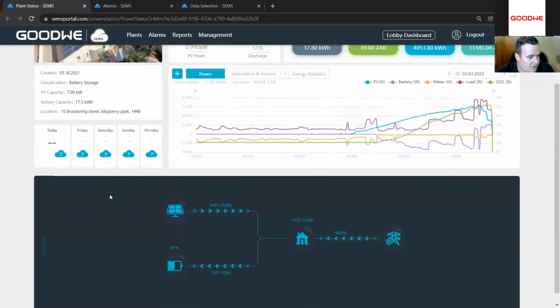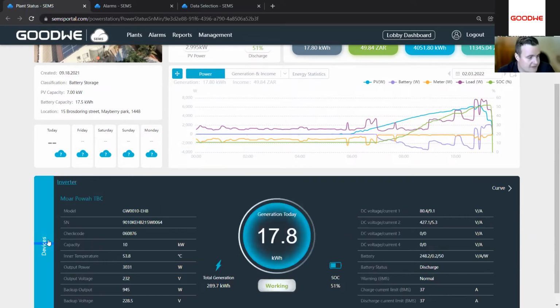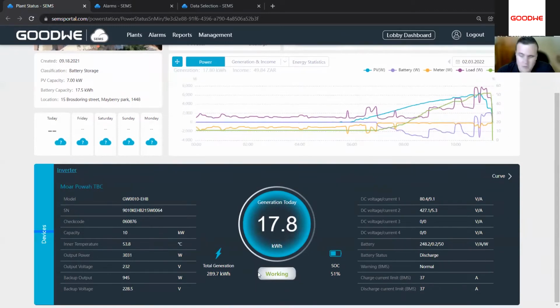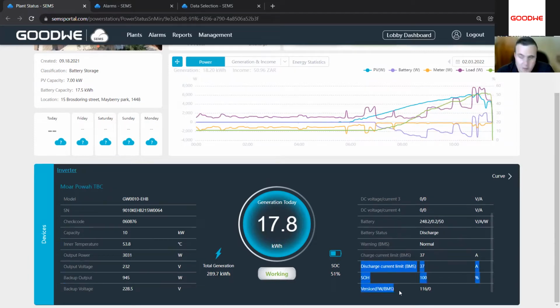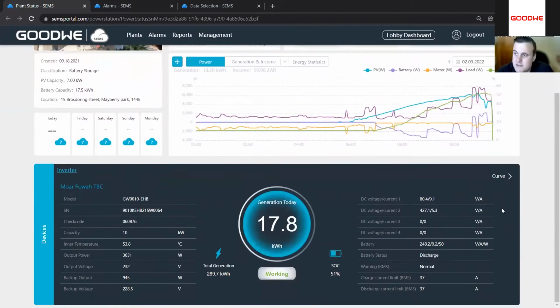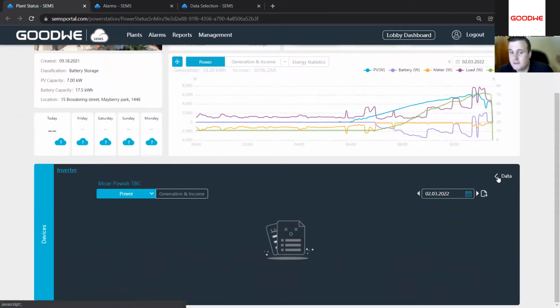In the general plant overview, we actually have a lot of information available to us. Here we can see the flow diagram, and on the side we can go into devices. Once you go into devices, we can see all the relevant information from our inverter: the grid output power, the backup output power, the charge current limits from our BMS, the firmware version, state of health of our batteries, all the DC voltages and inputs. But next we have the curve. The curve is something that I use quite a lot when we're looking for problems. It's one of the first places you should come to have a look.